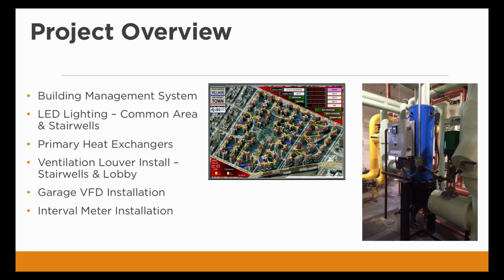The first thing we looked at was utilities, which were all included with the apartments. So the easiest utility for me to try and manage was the steam. We take district steam from Con Edison. There are 18 control rooms that feed the property heat and hot water, and every one of them has hot water heaters, with 100% redundancy in every control room. The easiest way for me to control it was to put in some kind of management system that would control the heat going up into the apartments. The only way to do that was to manage it from the basement area with apartment sensors. We put apartment sensors in three apartments in every line, and we were able to manage the heating system in the buildings through zone valves.